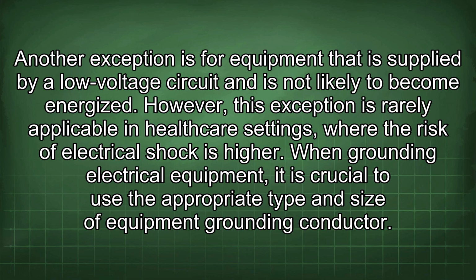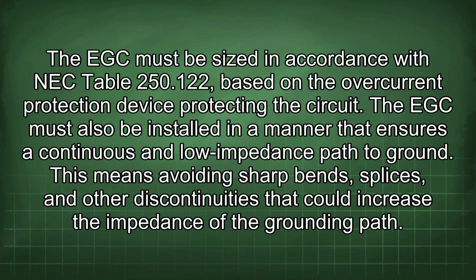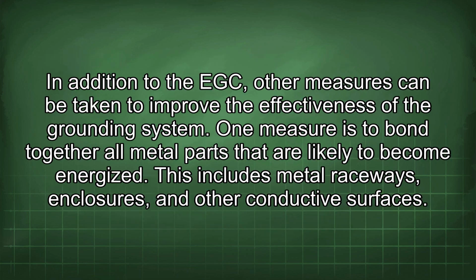When grounding electrical equipment, it is crucial to use the appropriate type and size of equipment grounding conductor. The EGC must be sized in accordance with NEC Table 250.122 based on the overcurrent protection device protecting the circuit. The EGC must also be installed in a manner that ensures a continuous and low impedance path to ground. This means avoiding sharp bends, splices, and other discontinuities that could increase the impedance of the grounding path. In addition to the EGC, other measures can be taken to improve the effectiveness of the grounding system.